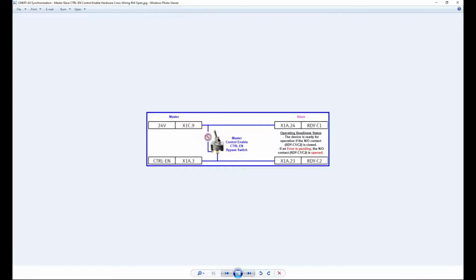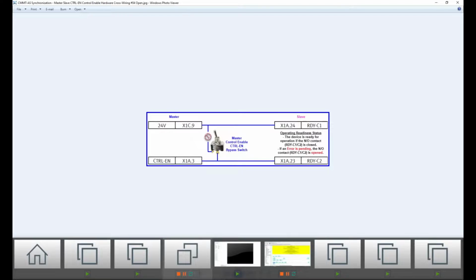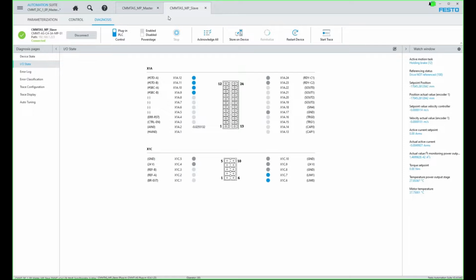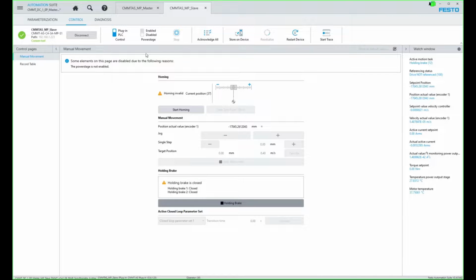Right now I've turned off the bypass here, and we need to make sure there's no faults. And we can look at that in this perspective right here. So the control enable is on right now. I'm not bypassing, and right now I have, on purpose, turned off the control enable to here, and I'm going to trigger a fault.